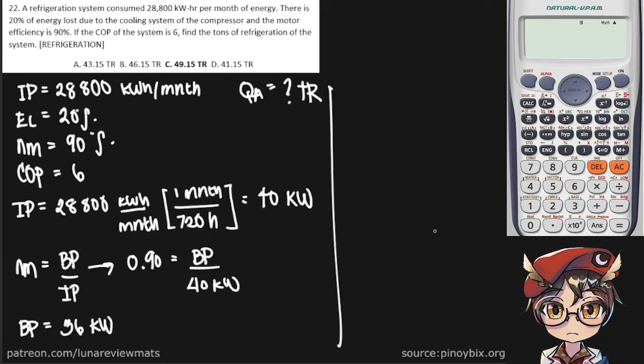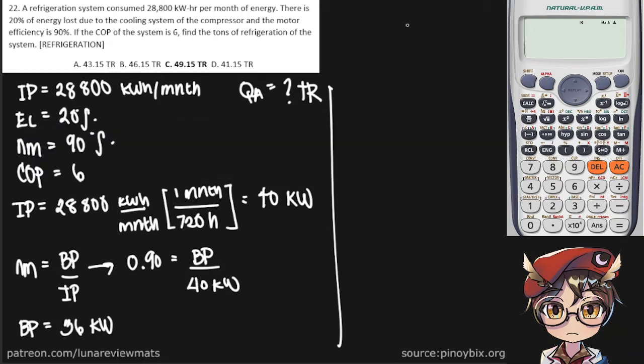So what is a coefficient of performance? Well, that is simply the ratio of useful heating or cooling, in this case cooling, provided to the work energy required. This is just the work of the compressor. Going by that definition, our COP is equal to the refrigerating effect divided by the work of the compressor.